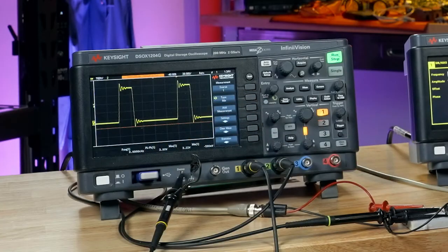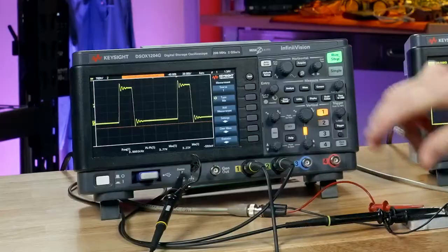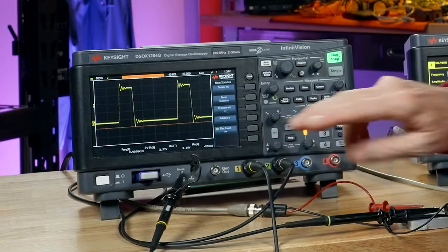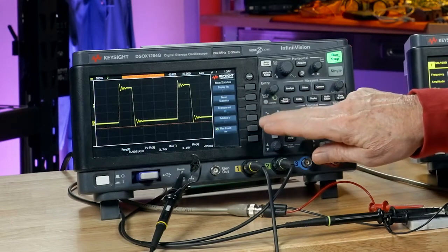Right now I've got 4 measurements on screen. That's the maximum on this scope. All of our higher performance scopes can show many more measurements than this, up to 10 measurements simultaneously. Now we can also turn on statistics for these 4 measurements, and I can see the average, the minimum, the maximum, the standard deviation, as well as the number of measurements that have been accumulated in this statistical set so far.